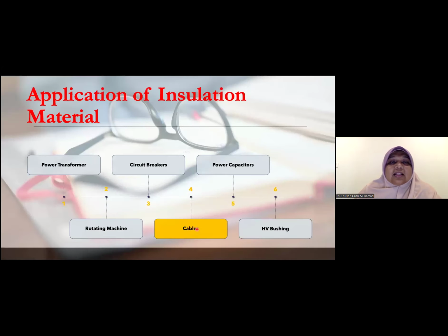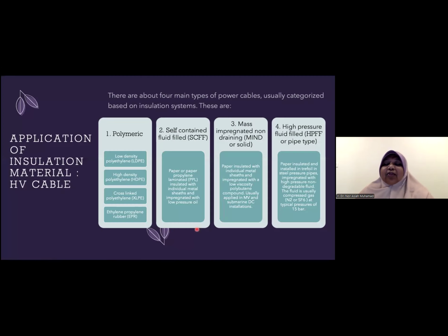Then we have the fourth equipment, which is the cable. Cables are one of the main, or the largest, equipment in the high voltage power system, because from the generation to the customer, the connection is through cable, whether it is a bare cable or an insulated cable. In this lecture, we will focus on the insulated cable. For the transmission line, normally the cable is uninsulated, a bare conductor without an insulator, because of heat dissipation, as it is a high voltage cable. But insulated cable is mostly used at medium voltage and at the distribution level, or as underground cable or submarine cable.